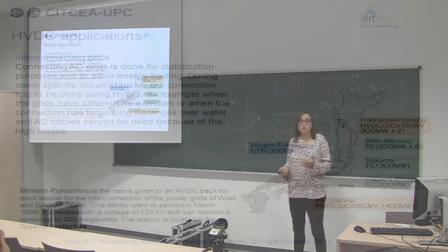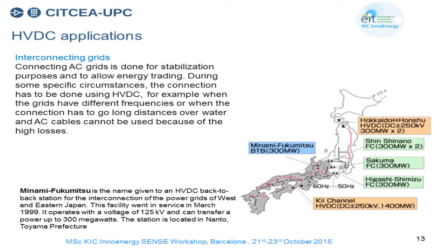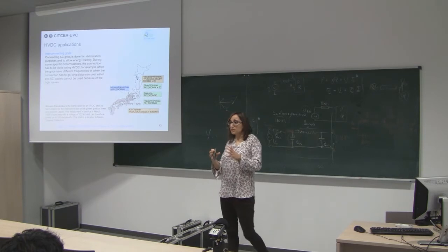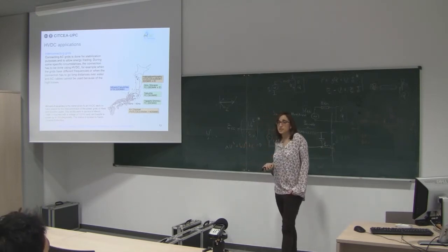Another application for HVDC is the interconnection of grids. You can also do this using AC technology, but in some cases HVDC is not just an option but the solution. For example, in Japan, part of the country works at 50 Hz and the other part at 60 Hz. The HVDC configuration called back-to-back, where the two converter stations are not distant from each other, enables power transmission between two grids that are asynchronous, meaning they work at different frequencies.